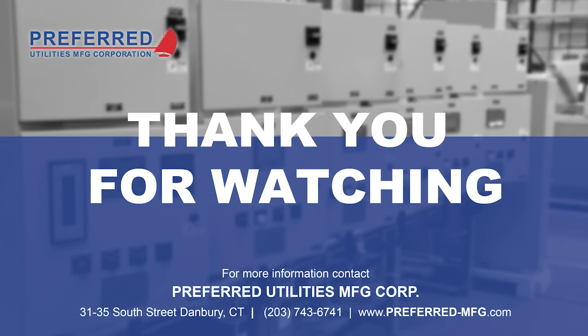And that's a good consideration because the oil in belly tanks just seems to sit for long periods of time. And even if you do generator runs every once in a while, you know, a quick generator test doesn't burn very much fuel. So the oil in your day tank can be relatively old. So in those situations where we have large belly tanks, we will usually do the sequence where we'll pump down the belly tank and get the old fuel out of it and top it off with fresh fuel that's been polished from the main tank.